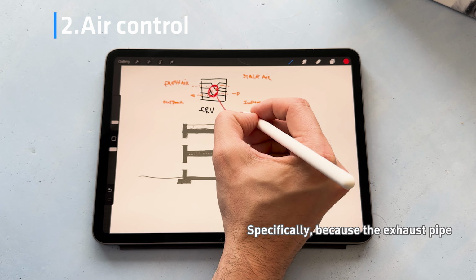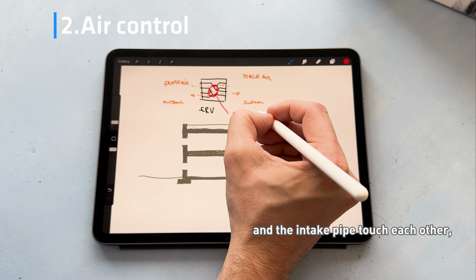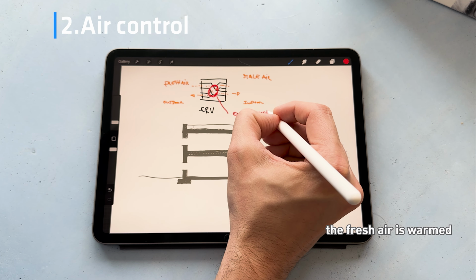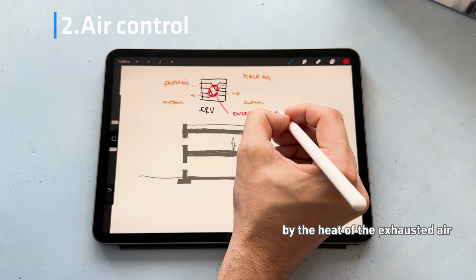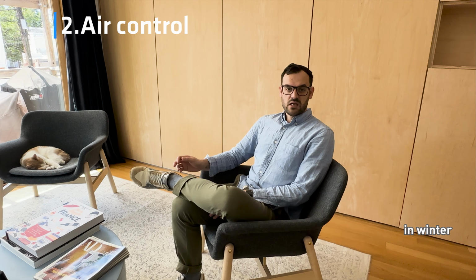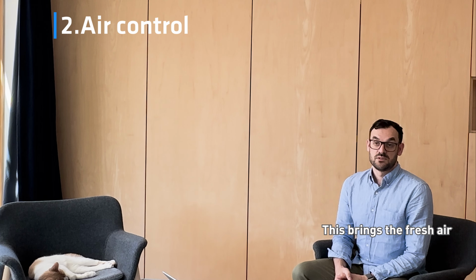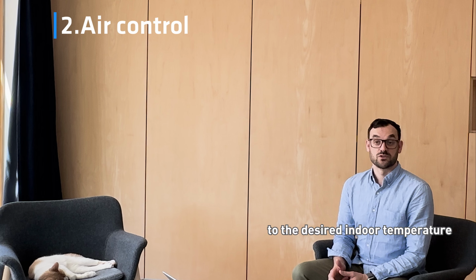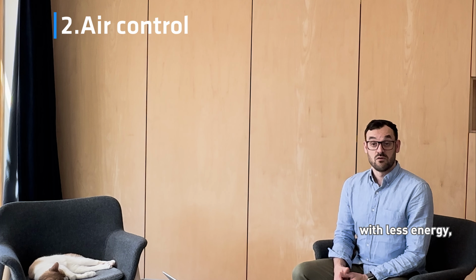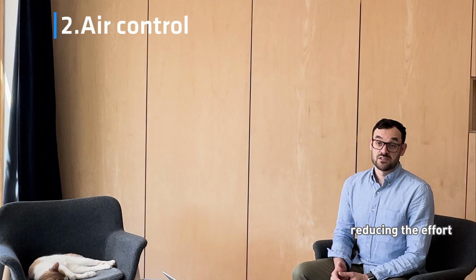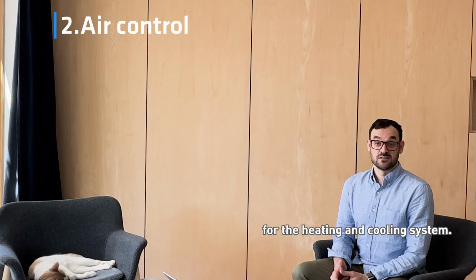Specifically, because the exhaust pipe and the intake pipe touch each other, the fresh air is warmed by the heat of the exhaust stale air in winter and cooled by the exhaust stale air in summer. This brings the fresh air temperature closer to the desired indoor temperature with less energy, reducing the effort for the heating and cooling system.